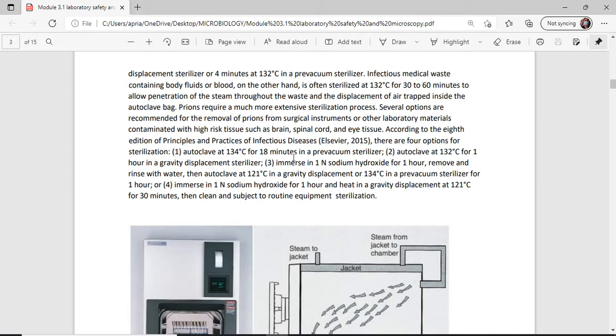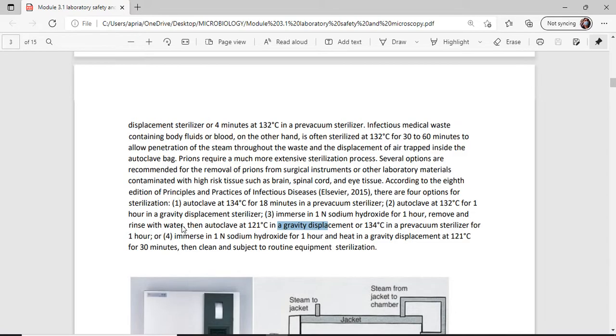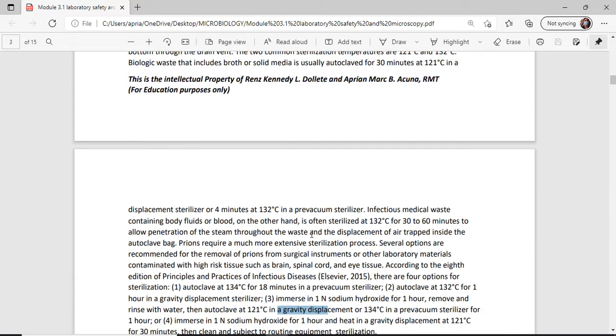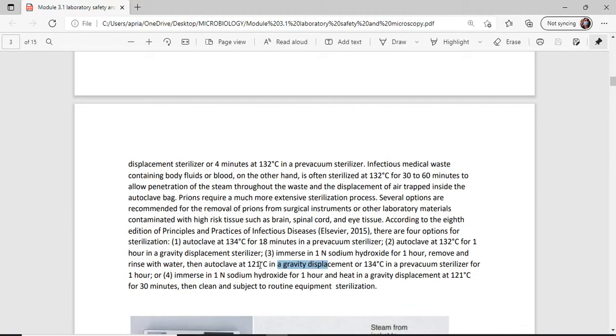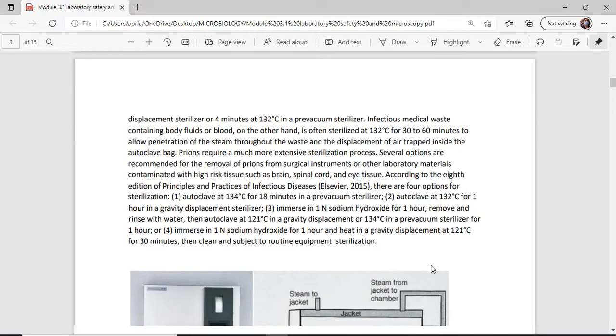Next is immerse in a 1 normal sodium hydroxide for 1 hour. After letting it sit immersed, you need to remove and rinse it with water. Then autoclave it in the same autoclave as before, at 121 degrees Celsius, or at 134 degrees Celsius if using a pre-vacuum sterilizer, for 1 hour.